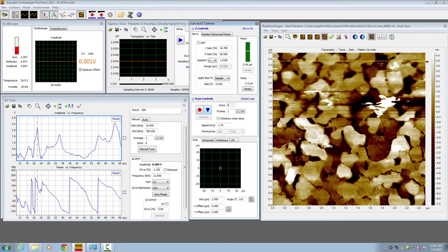The difference between using contact mode and AC mode imaging a sample in liquid is that AC mode does not disturb some of the soft molecules or soft materials on the sample as much as contact mode does. So compare this image to the earlier contact mode image. There are several contamination spots on the sample. In the contact mode they appear to have a lot of lateral movements, while in AC mode, the contamination no longer has the lateral movements.